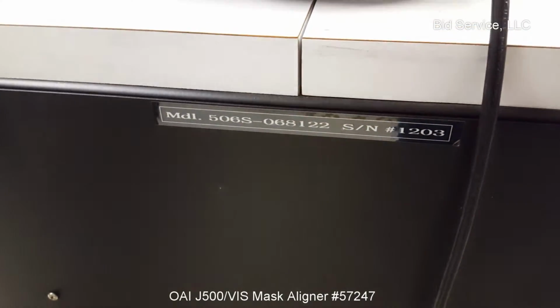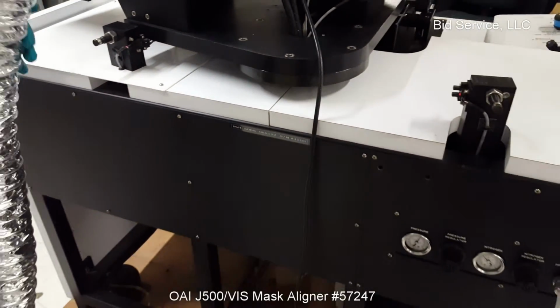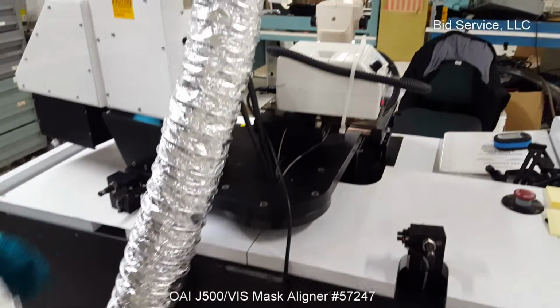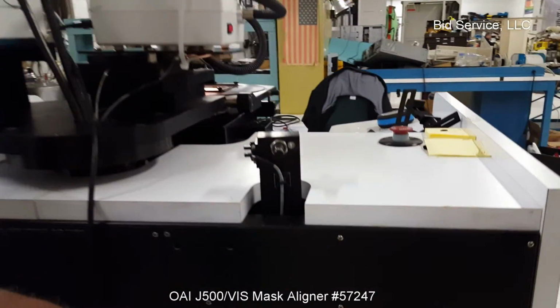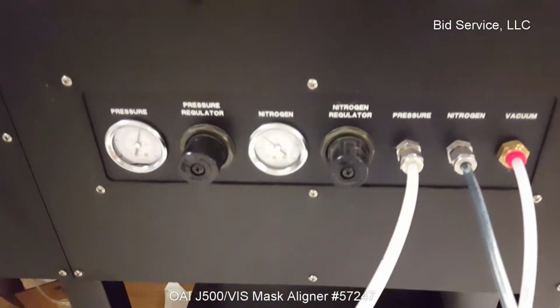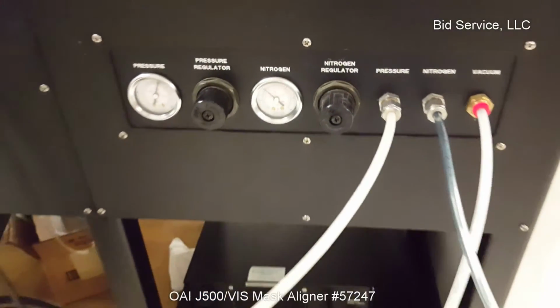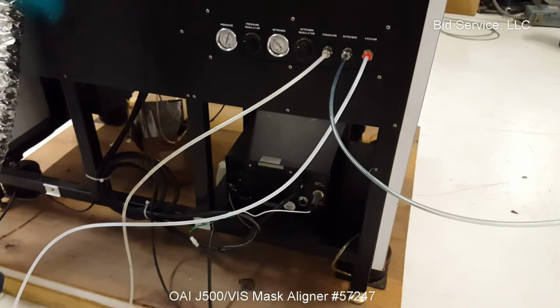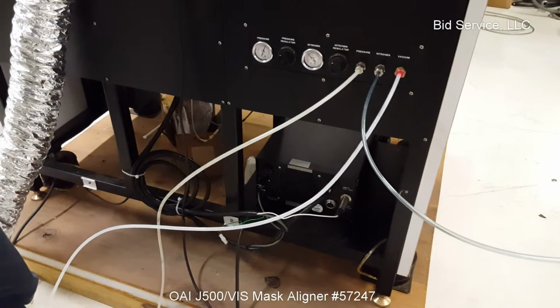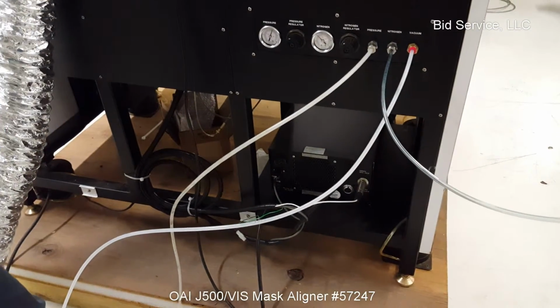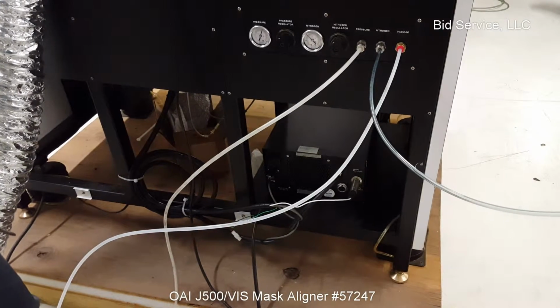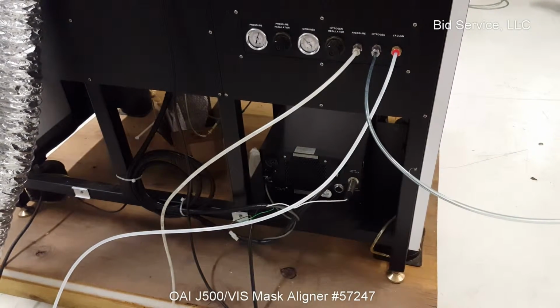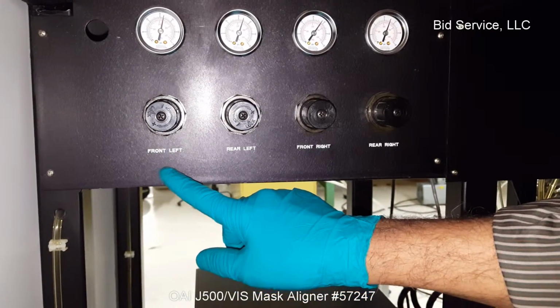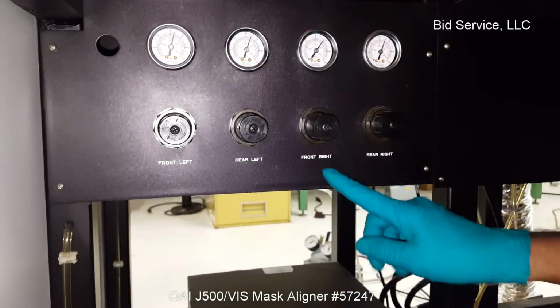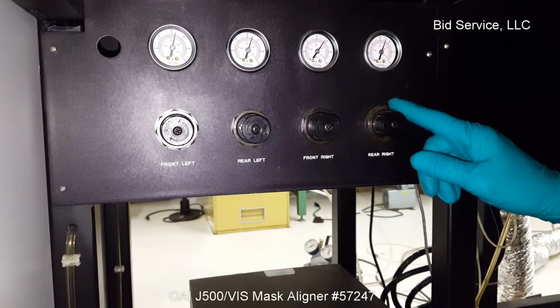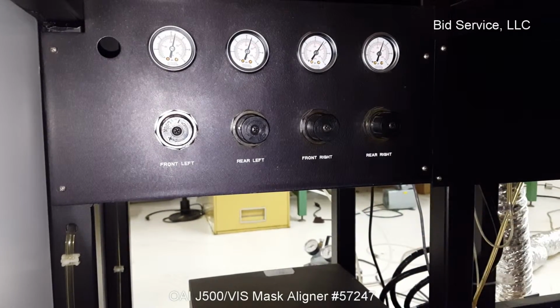The system requires a facilities exhaust connection, and there are adjustments for the compressed air and nitrogen on the pneumatic panel. The system is mounted on vibration isolation tables, and there are 4 bellows under the table. The pressure in each bellow can be adjusted. There are regulators for the front left, rear left, front right and rear right vibration isolation bellows under the system.